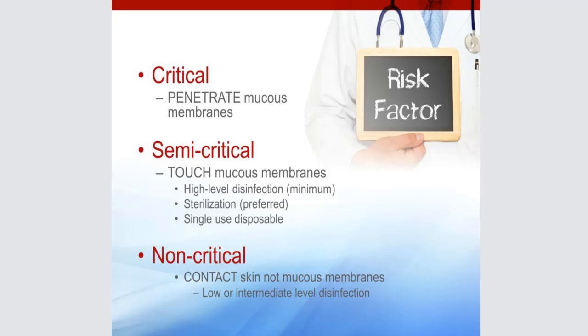Finally, last but not least, are the non-critical items. These just contact the skin but not the mucous membranes. So that would be things like a pulse oximeter, a blood pressure cuff, the x-ray head. These just need to be surface disinfected with a low or intermediate level disinfectant.